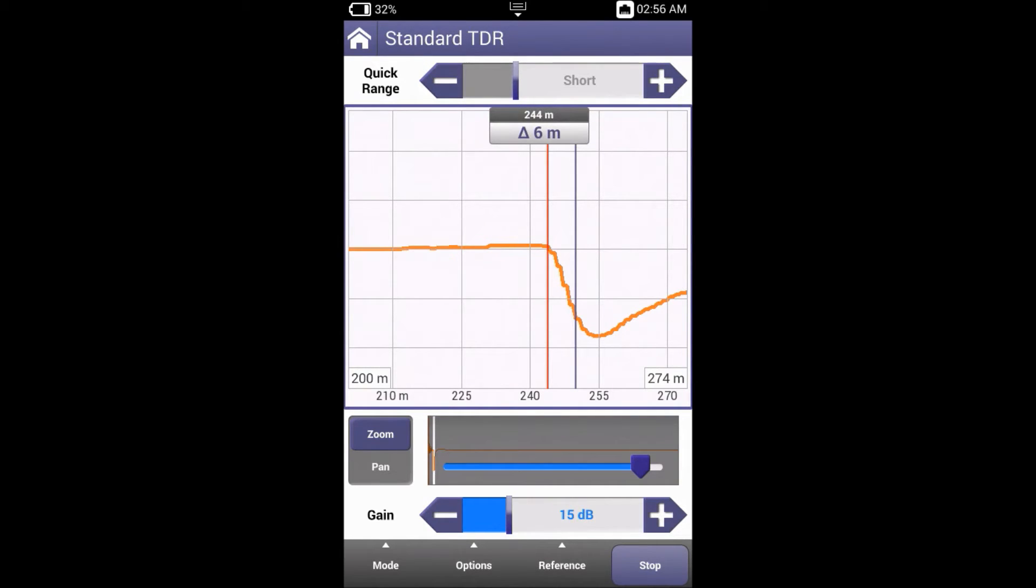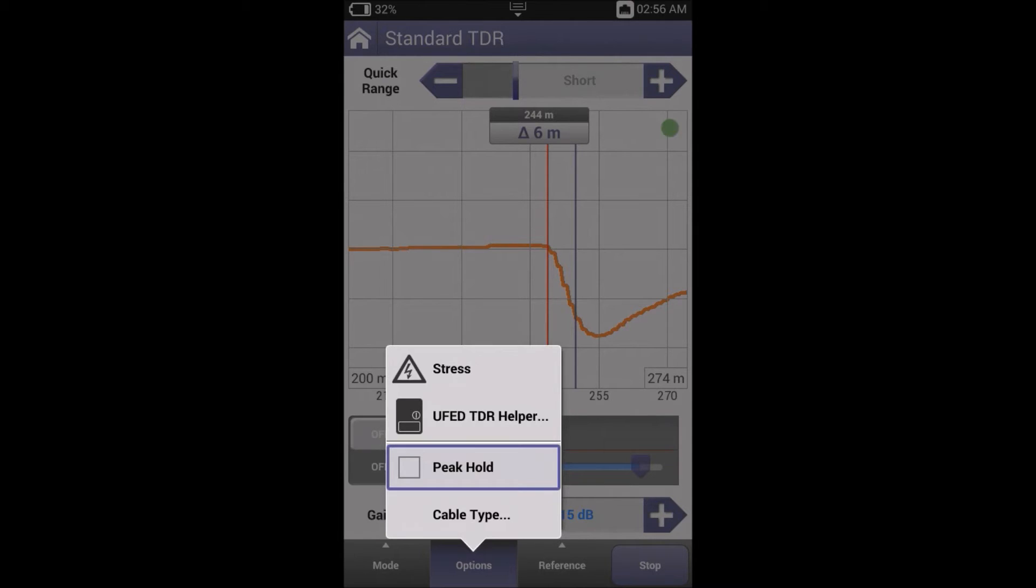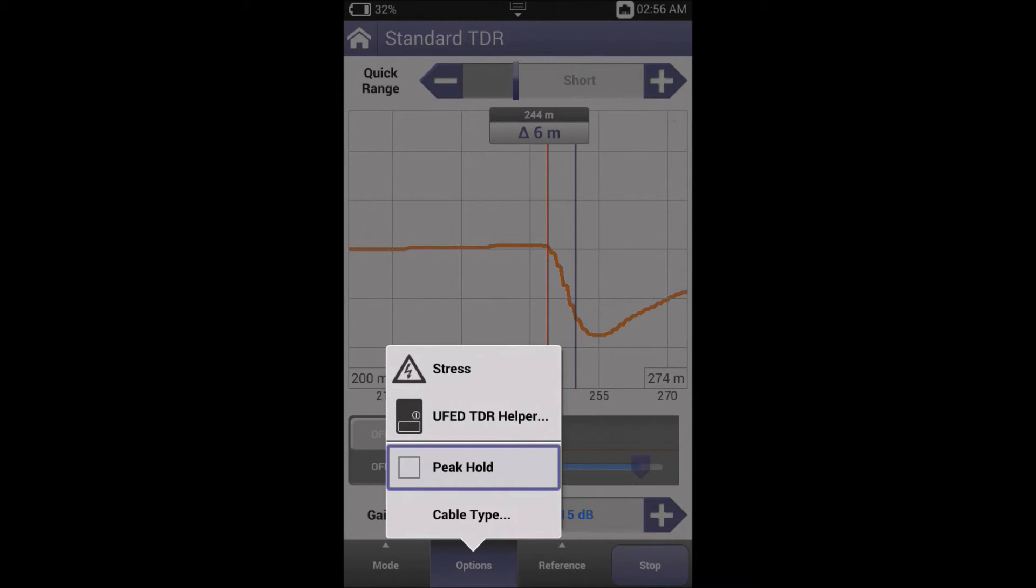One of the more difficult problems to locate is a conductor that is partially broken. This condition is referred to as a high resistance open. The difficulty is due to the dynamic nature of the fault. In some instances, the resistance lowers and the line appears fine, only to have the resistance increase, resulting in unsatisfactory service. The ONX incorporates two manual features which can be used separately or in combination to help locate HR opens. These features are peak and stress modes.